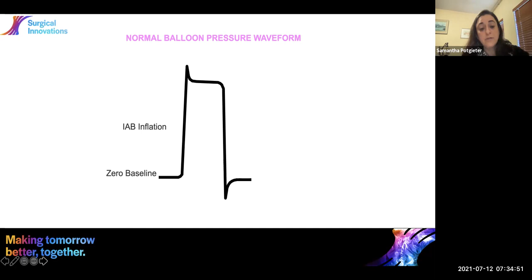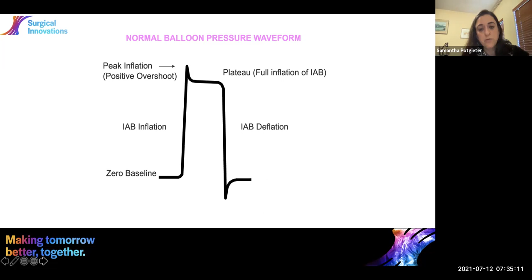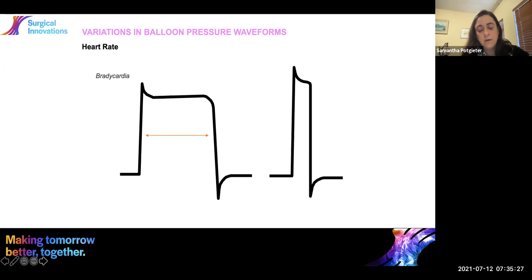So there's your zero baseline. There's where the balloon inflates. That's the peak inflation. That's the plateau. In other words, the balloon is full. And that's where it deflates. So that's typically what you want to see, is that kind of a shape there. But when you have hemodynamic changes to the patient, you're going to have a balloon that looks a bit different. So if we have changes in our heart rate, there's a much longer inflation there. And that's a bradycardia. And a much shorter inflation here is a tachycardia.